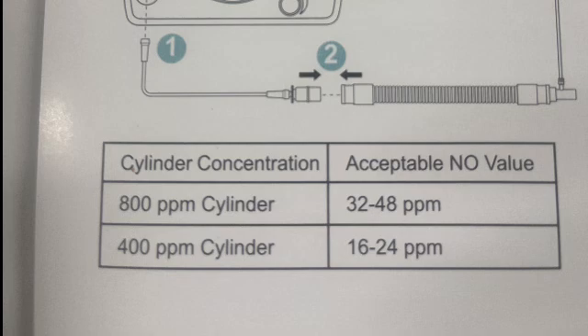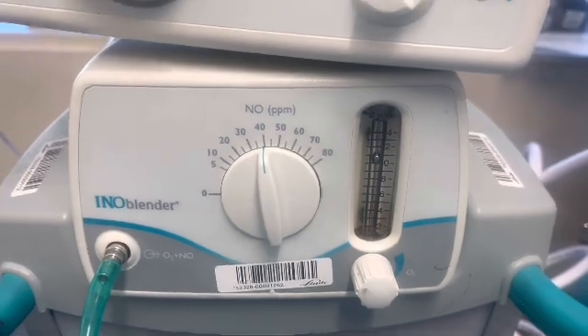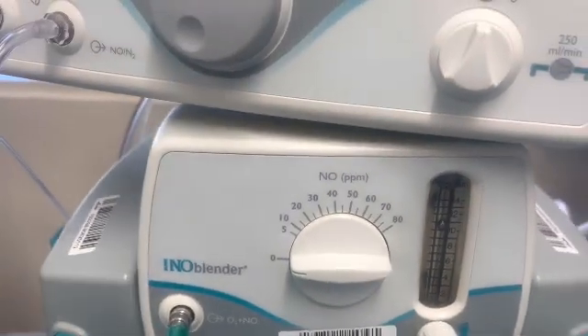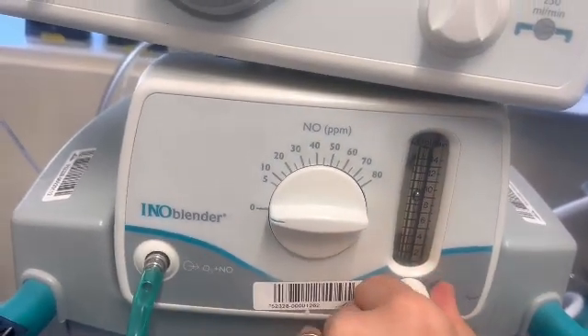The acceptable NO or nitric oxide values to enable a passed INOblender test are 32 to 48 parts per million. When you're happy that the values are within range, you can turn the dose to 0 and turn off the flow meter.